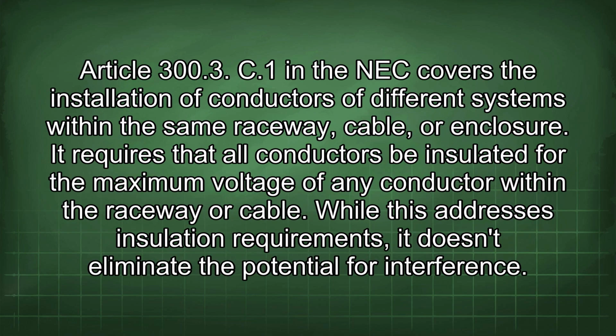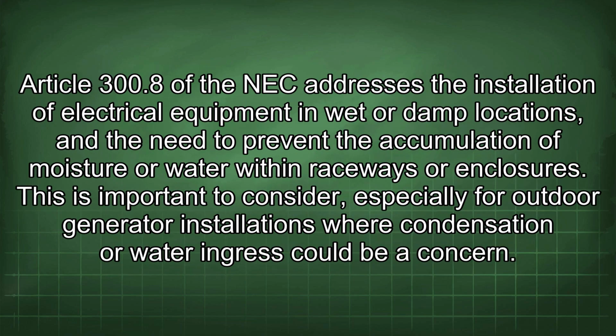Article 300.3(C)(1) in the NEC covers the installation of conductors of different systems within the same raceway, cable, or enclosure. It requires that all conductors be insulated for the maximum voltage of any conductor within the raceway or cable. While this addresses insulation requirements, it doesn't eliminate the potential for interference. Article 300.8 of the NEC addresses the installation of electrical equipment in wet or damp locations and the need to prevent the accumulation of moisture or water within raceways or enclosures. This is important to consider, especially for outdoor generator installations where condensation or water ingress could be a concern.